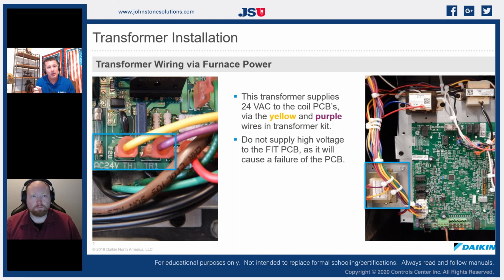So, a lot of these components have additional power supplies that need to be installed with them. So if we're talking about a Daikin FIT and we're installing that electronic expansion valve cased coil, we're going to add a separate transformer inside the furnace that's going to feed power to our new EEV coil. What a lot of guys and gals are not understanding is that transformer is going to be polarity sensitive. So with transformers, we really need to ground our common side of our transformer so that we have a path of flow for our current.